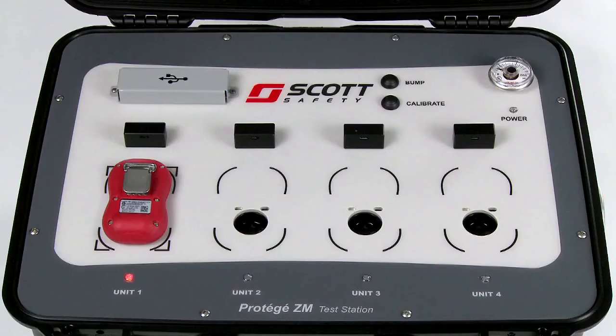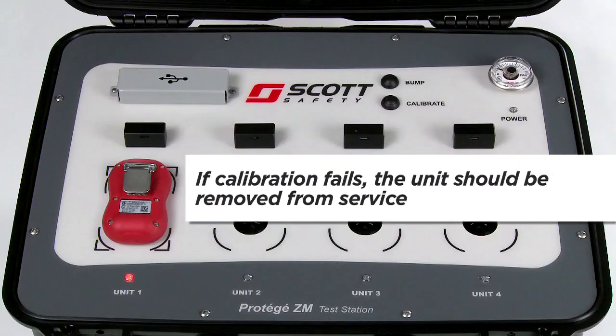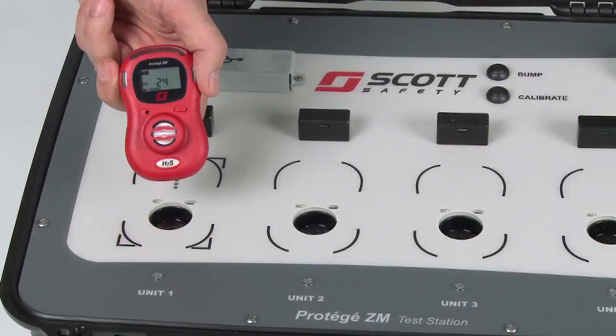If the test bay LED lights up red, it indicates the monitor could not be calibrated. If a monitor cannot be calibrated, it should be taken out of service and replaced. CO and H2S monitors can also be hibernated to save battery power. You can hibernate your CO and H2S monitors up to 1 year to extend the life of your monitor.